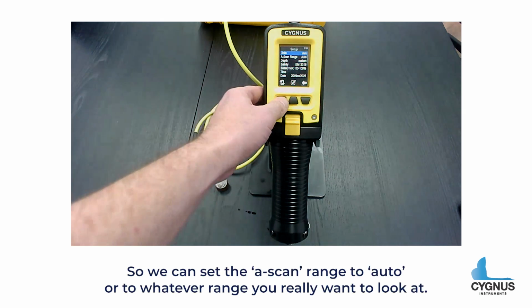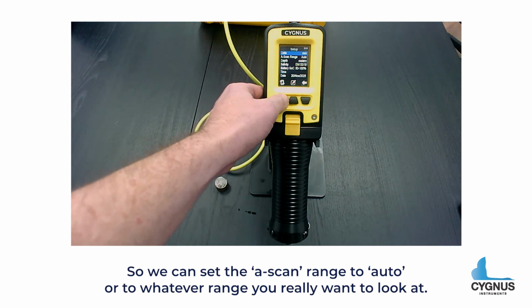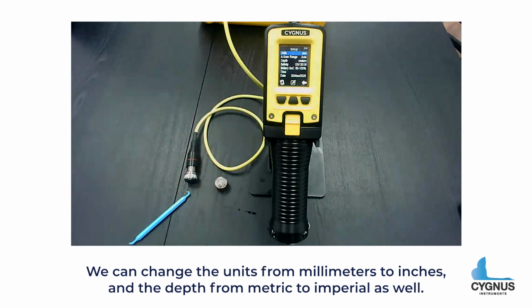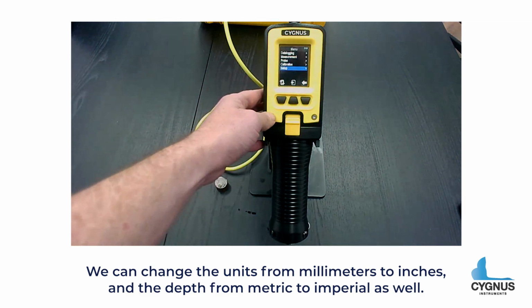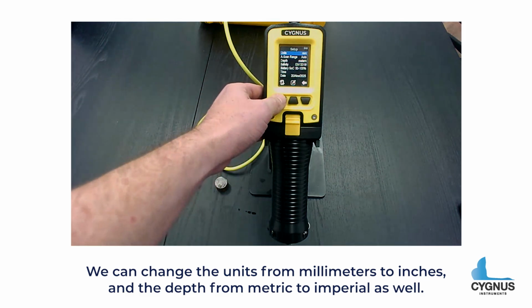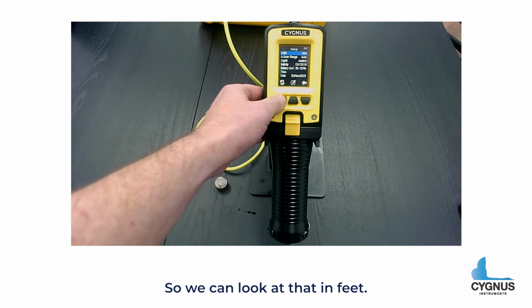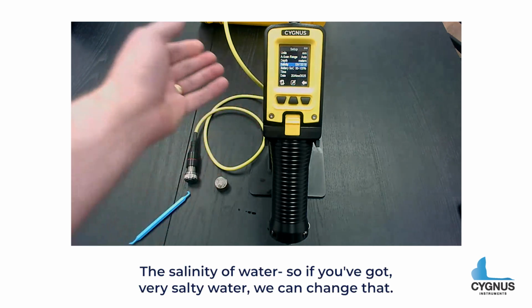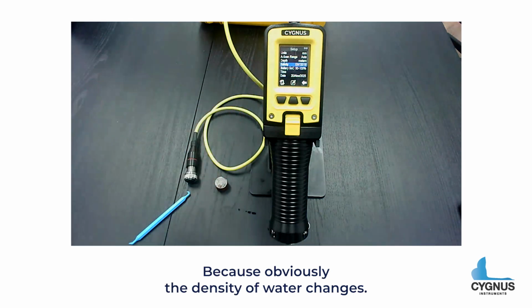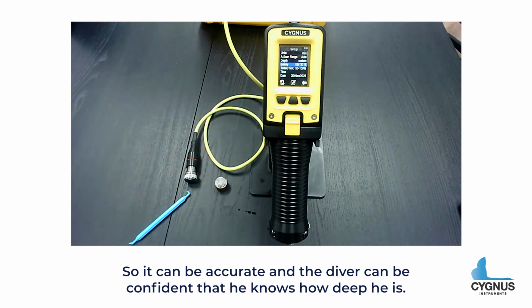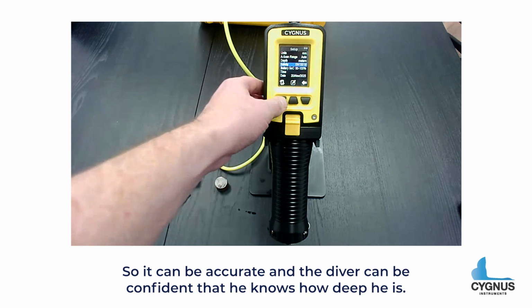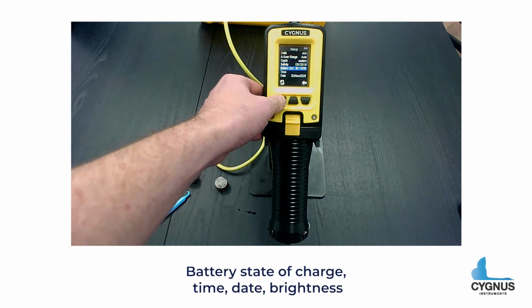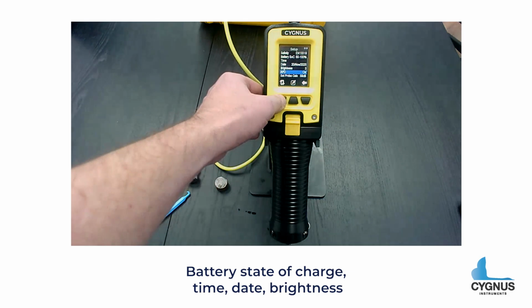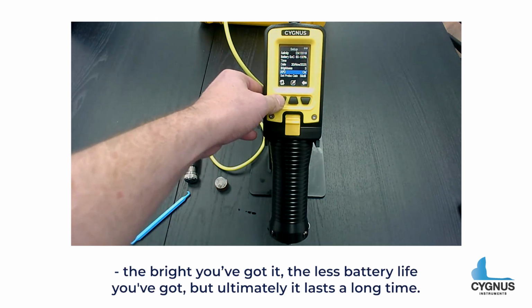So we can set the A scan range to auto, or to whatever range you really want to look at. We can change the units from millimeters to inches, and the depth from metric to imperial as well, so you can look at that in feet. The salinity of water: if you've got very salt water, we can change that, because obviously the density of water changes. So it can be accurate and the diver can be confident that he knows how deep he is. Battery state of charge. Time, date, brightness. The brighter you've got it, the less battery life you've got, but ultimately it lasts a long time.